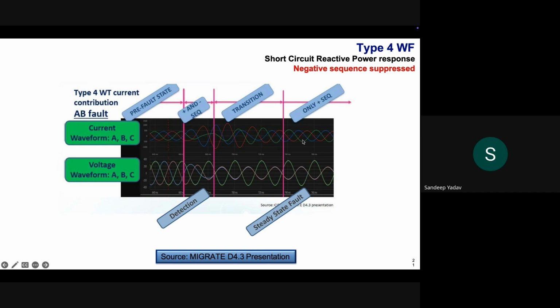So in the upcoming slides, where we take the case studies from the real systems in the Indian grid, real faults, we will see what the behavior of the fault current of the inverter-based resource is in case of phase-to-phase faults, or in case of phase-to-ground faults, where we will see the zero sequence coming into play.